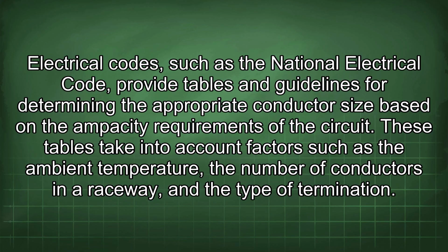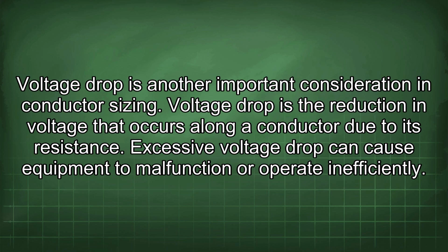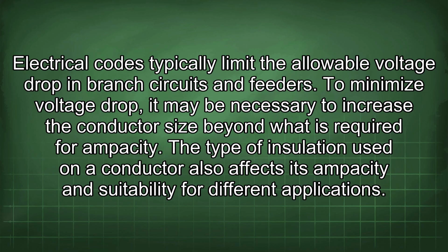These tables take into account factors such as the ambient temperature, the number of conductors in a raceway, and the type of termination. Voltage drop is another important consideration in conductor sizing. Voltage drop is the reduction in voltage that occurs along a conductor due to its resistance. Excessive voltage drop can cause equipment to malfunction or operate inefficiently. Electrical codes typically limit the allowable voltage drop in branch circuits and feeders. To minimize voltage drop, it may be necessary to increase the conductor size beyond what is required for ampacity.